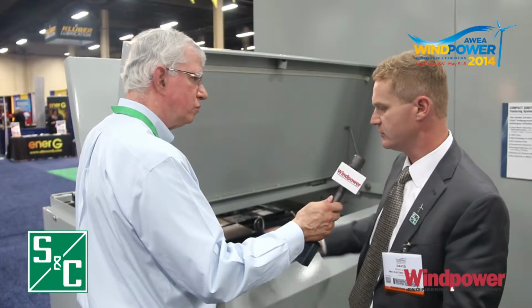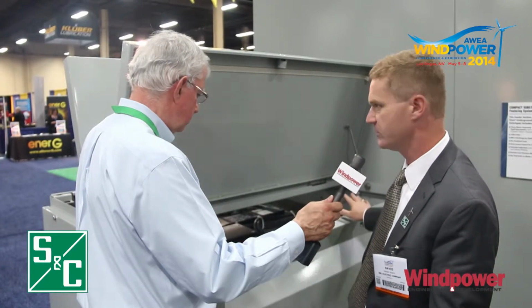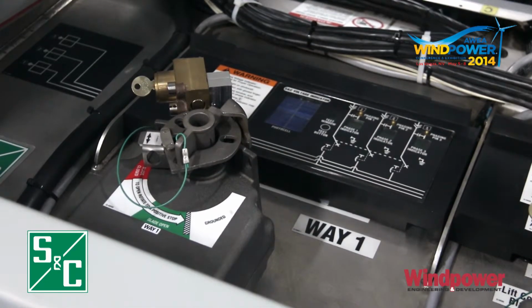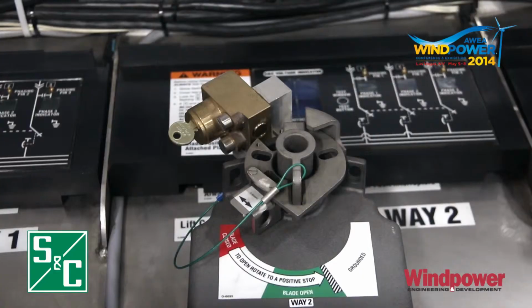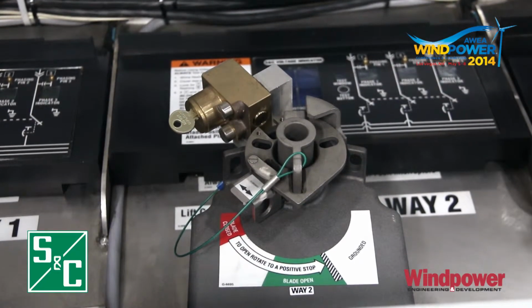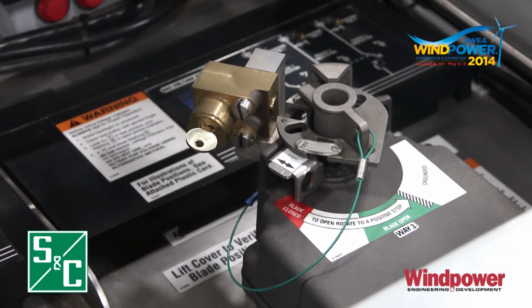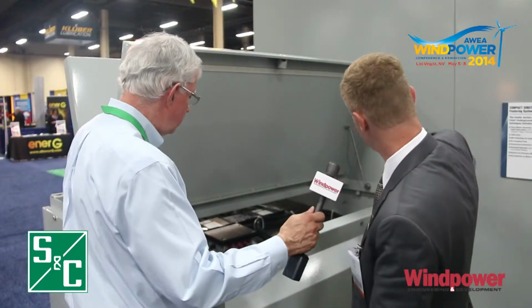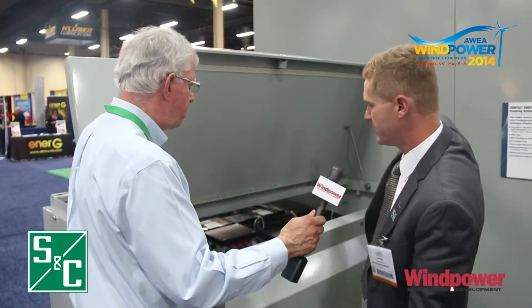So you would have 3 collection feeders coming into this at 35 kV into this switchgear. This is a 3-way Vista, whereas the turbine Vista was a 1-way Vista. This has 3 ways coming in, and then it goes from here into these next bays that we can look at as well.